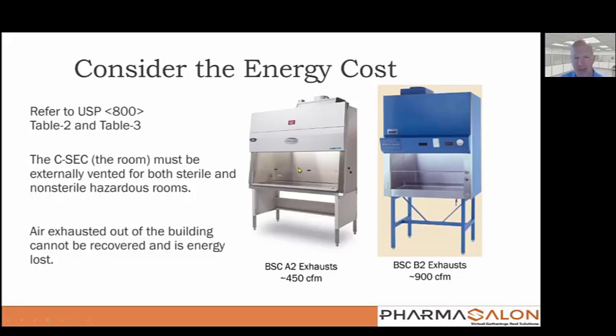It is allowed, and is stated that it is allowed in chapter USP 800, because it has an internal recirculation around HEPAs, right, so we're never recirculating potentially dirty air. It only exhausts about 450 CFM on average. Every model, whether it's 4 foot or 6 foot, will vary, but let's put an average number of 450. Now, some would say, well, I'm concerned about volatilizing chemicals or other things, so we're going to go with a B2 cabinet. With a B2 cabinet, there's no internal recirculation whatsoever. So you're actually going to end up exhausting twice as much air out of that hazardous sterile buffer.